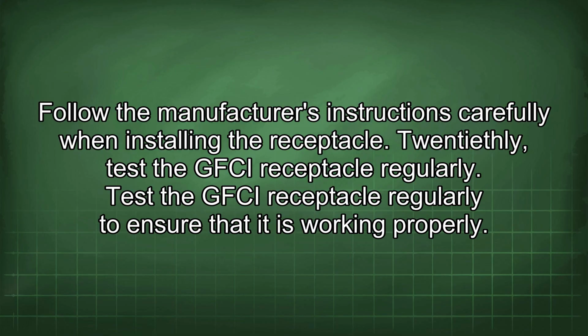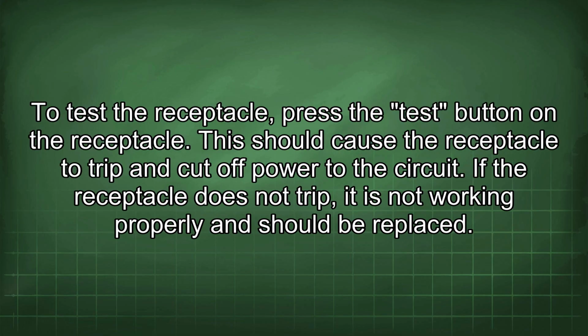20th, test the GFCI receptacle regularly. Test the GFCI receptacle regularly to ensure that it is working properly. To test the receptacle, press the test button on the receptacle. This should cause the receptacle to trip and cut off power to the circuit. If the receptacle does not trip, it is not working properly and should be replaced.